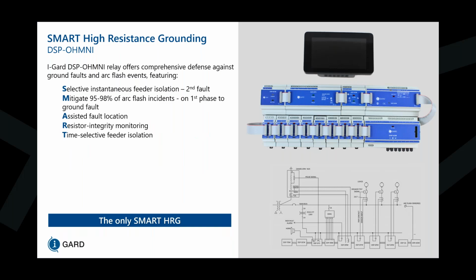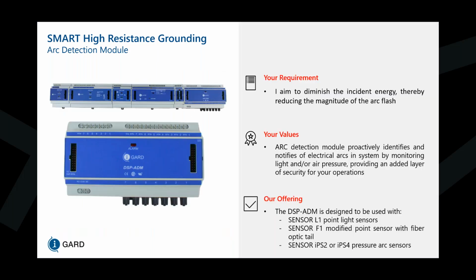In this case, with high resistance grounding and the combination of the arc flash relay, we can mitigate 95 to 98% of arc flash incidences by picking up on phase to ground faults through our HRG system, which will limit fault current to 5 amps. And phase to phase and 3-phase failures can be picked up by the arc flash sensors. So the arc detection module, the aim is to diminish the incident energy, thereby reducing the magnitude of the arc flash by tripping the upstream breaker.